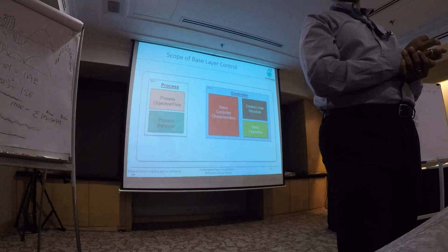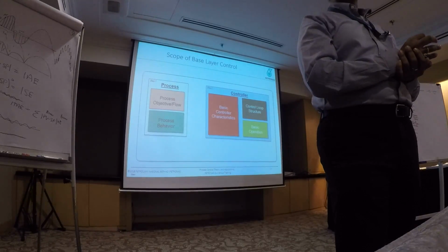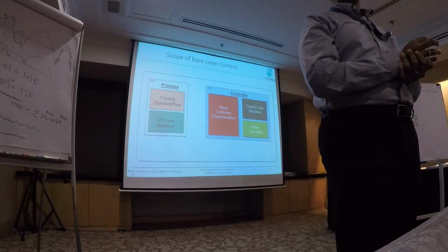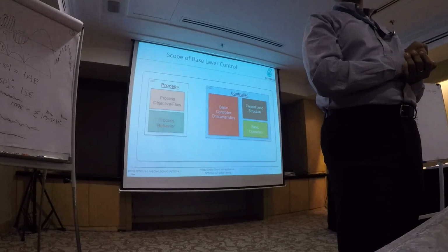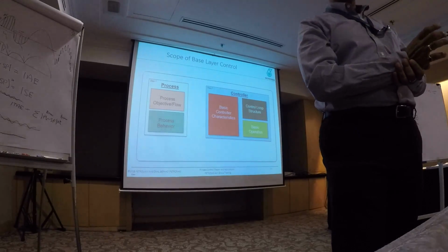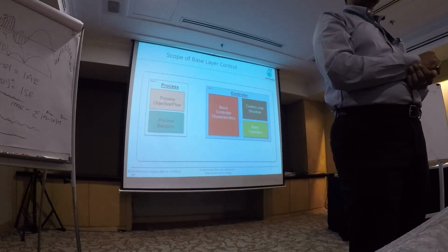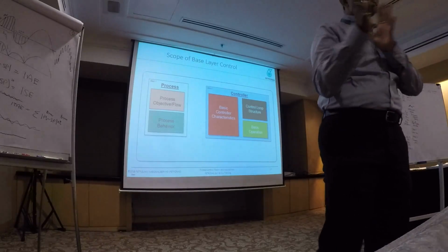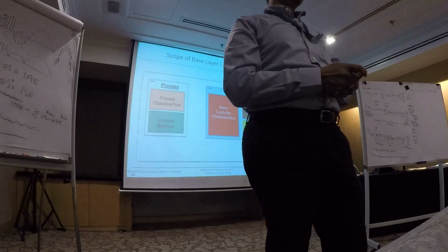I was thinking, let's say you're taking the data every second and you see it's noisy. What if you change it to every 2 or 3 seconds and take only one data point? Is that acceptable? Yes, that's almost like taking a moving average of the data. I can't remember which DCS has a moving average filter, but you could do that, if you already know that it's noise.